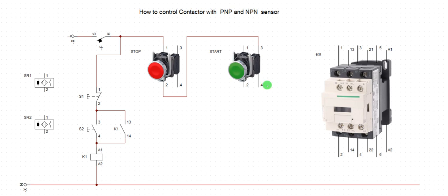So now I want to do this wiring according to what I have here. I have here starting from my supply to 1. And I have here 2 to terminal 1 of my stop button. Then 2 should go to 3 to feed this one. Then 4 should go to A1. This is my 4, I'm taking it to A1. Then A2 should go to neutral. So I'm going to wire according to what I have here.